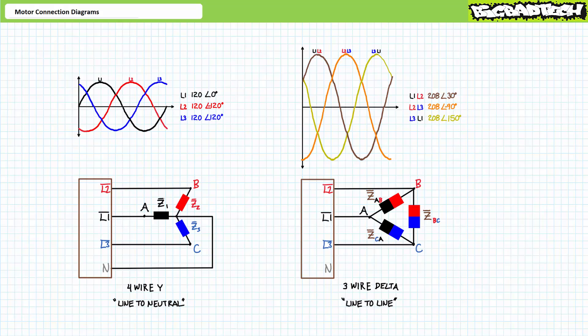This is not what is meant by the term dual voltage. A single three-phase AC system with two available voltages — line-to-neutral and line-to-line — is still a single system. The term dual voltage more appropriately means two system voltages. Manufacturers offer dual voltage motors so products can meet the needs of industrial applications in various countries characterized by different electrical distribution voltages. One system is designated as the low voltage option and the other as the high voltage option with totally different line-to-neutral and line-to-line voltages. Low voltage configurations are associated with parallel windings, whereas high voltage configurations are associated with series windings.